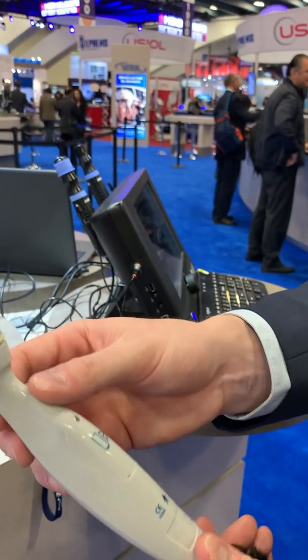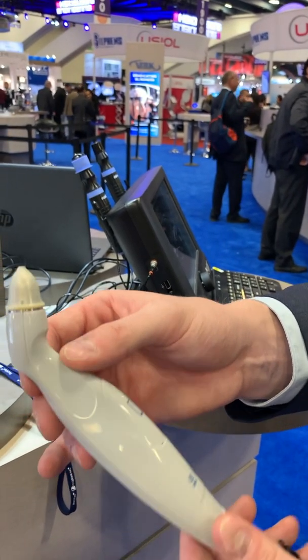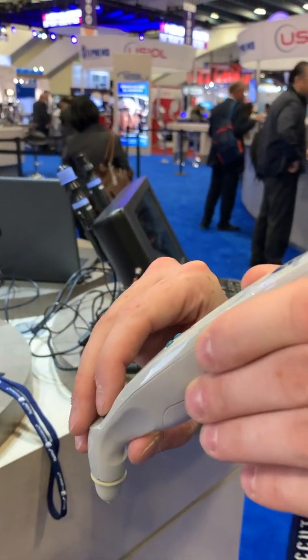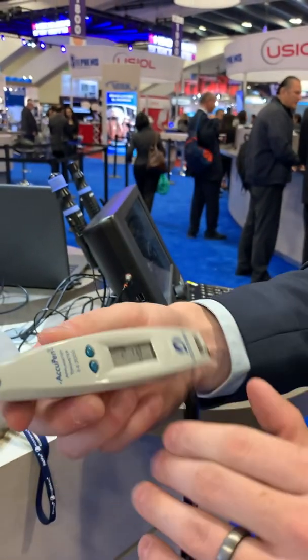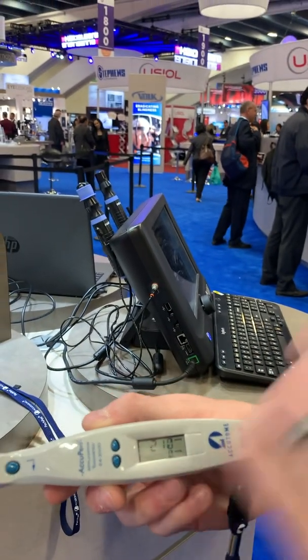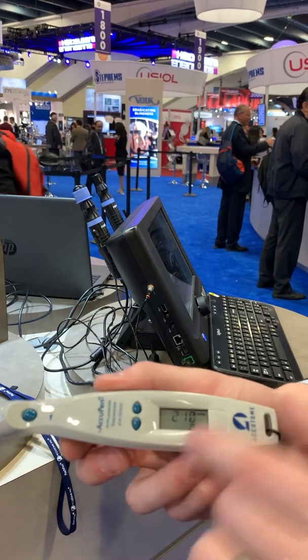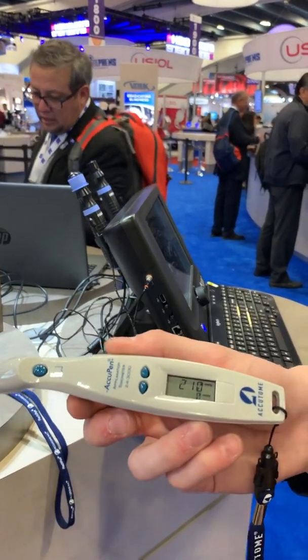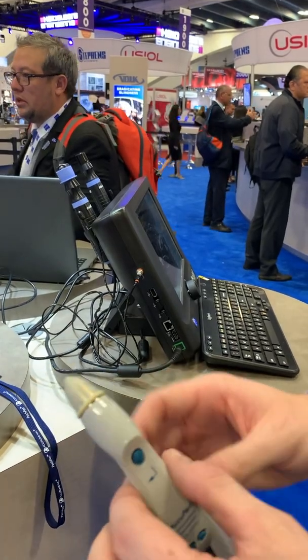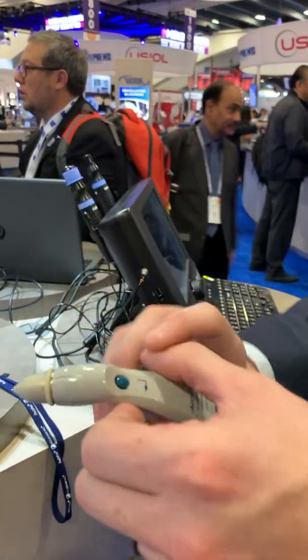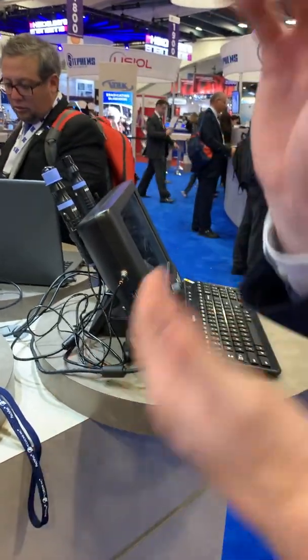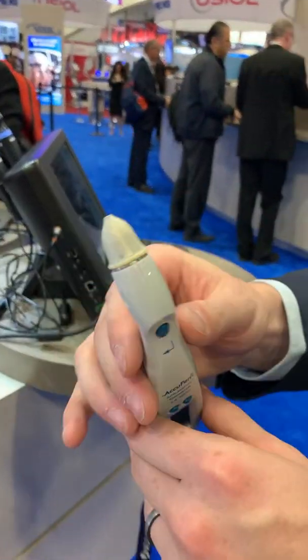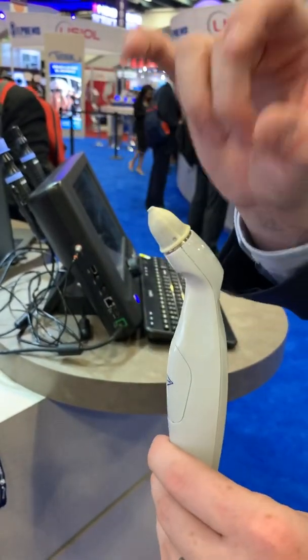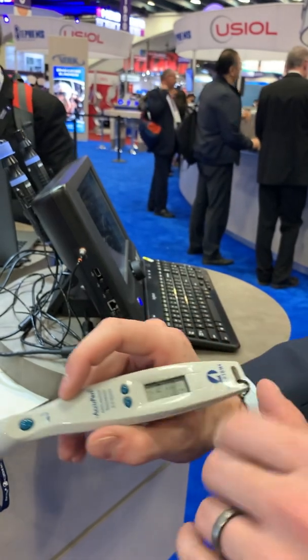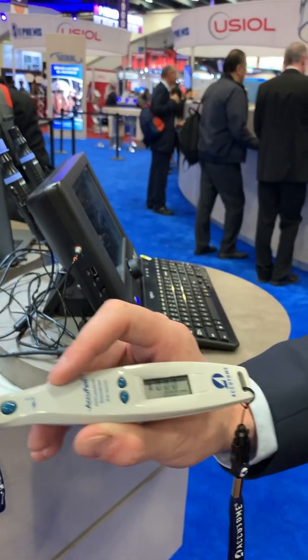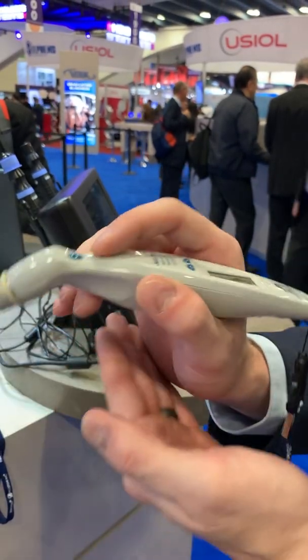Probe up. And turn the probe up. Again press. And again, probe down. Again press. It gives us a calibration number of 210. This particular unit has a calibration number of 205. So within plus or minus 20 of that number, we know that we're reading correctly. All we're doing is showing how much gravity is going to be affecting our reading. That way we can take measurements lying down, we can take measurements in a seated position. For any crazy reason you needed to take a reading moving up, it just allows for the impact of gravity on that reading. Once I have my reading, I would start my reading, and I'm ready to go. Again, I'm starting my action button, tapping on the cornea.